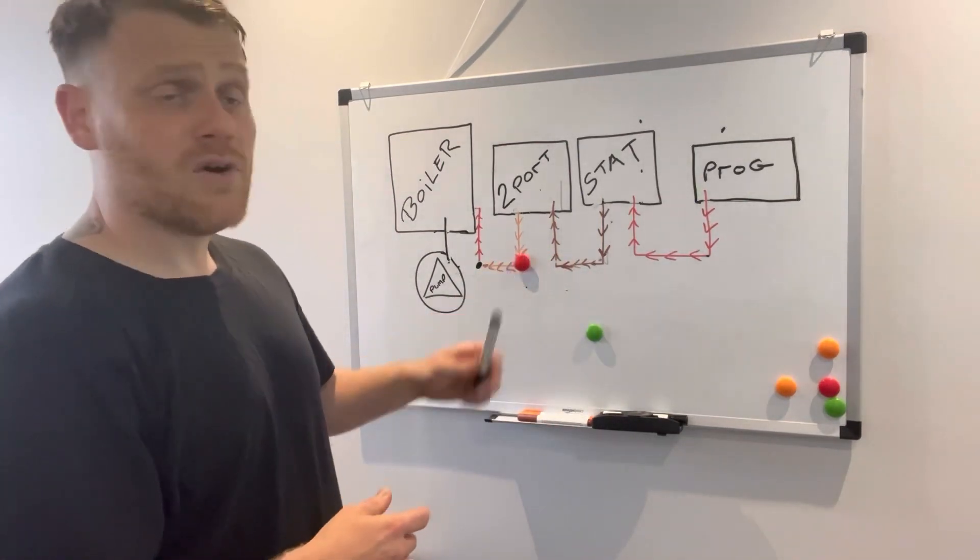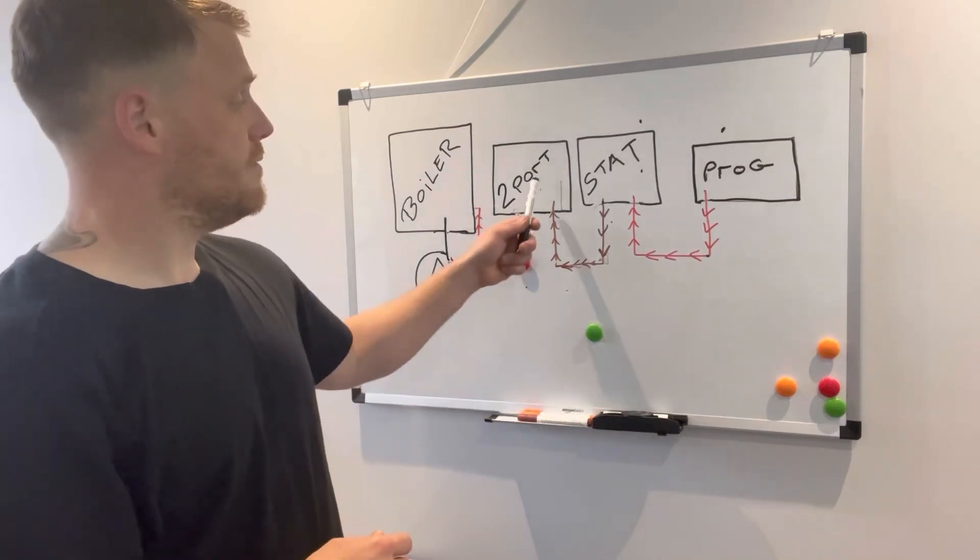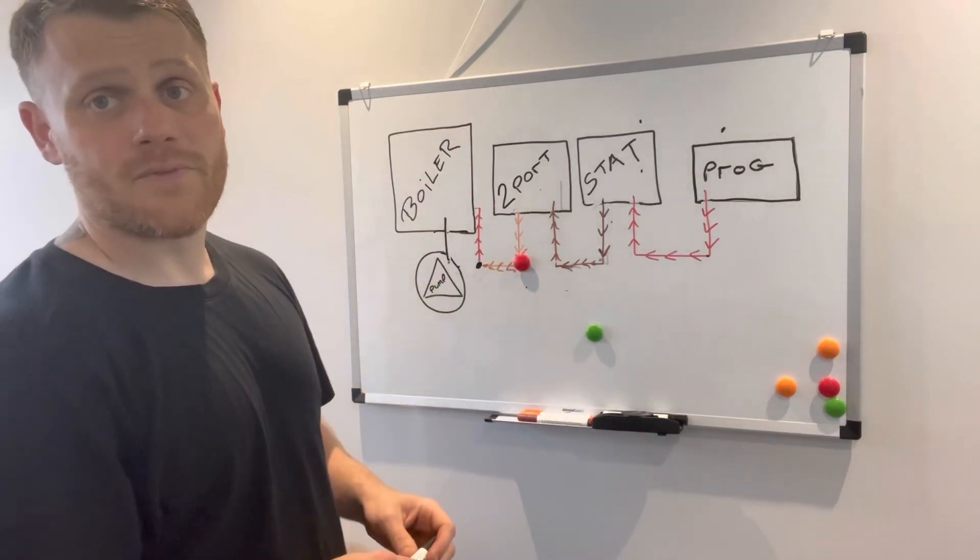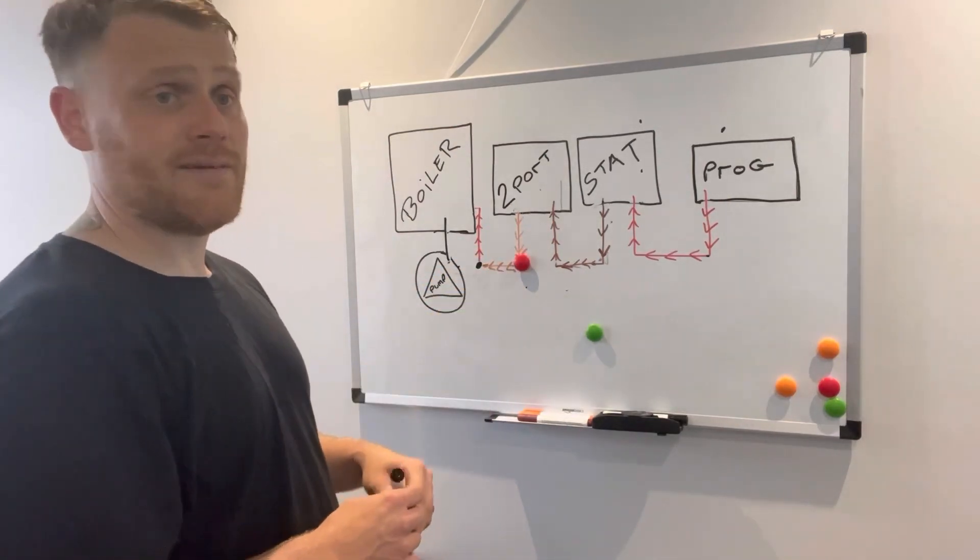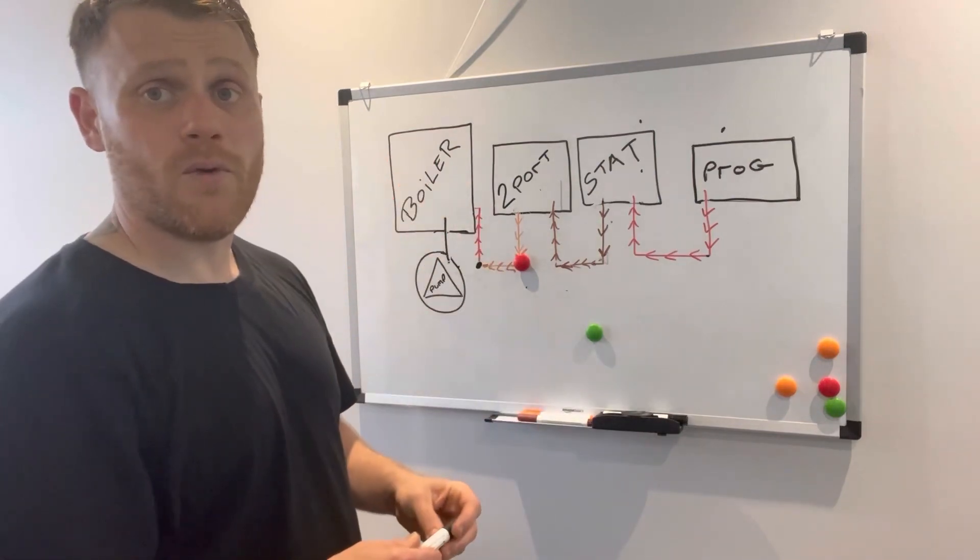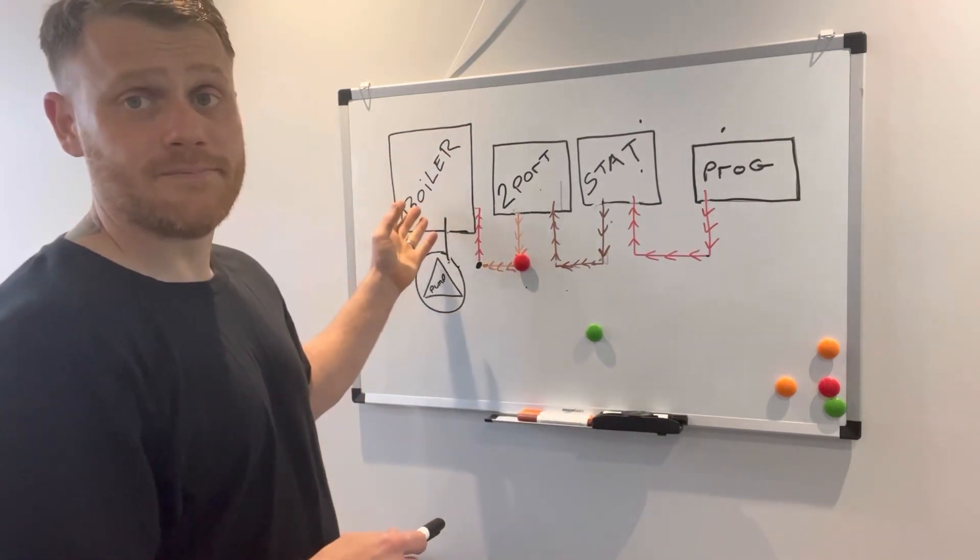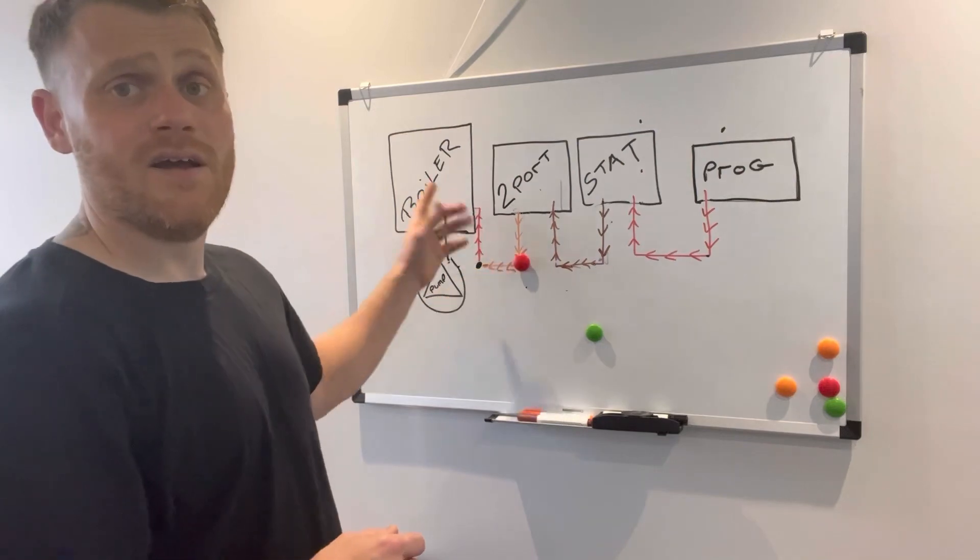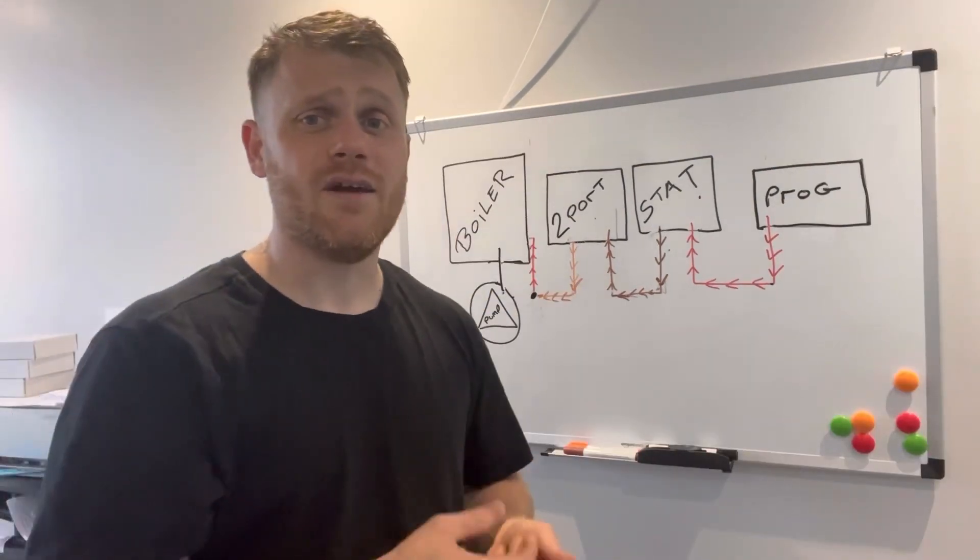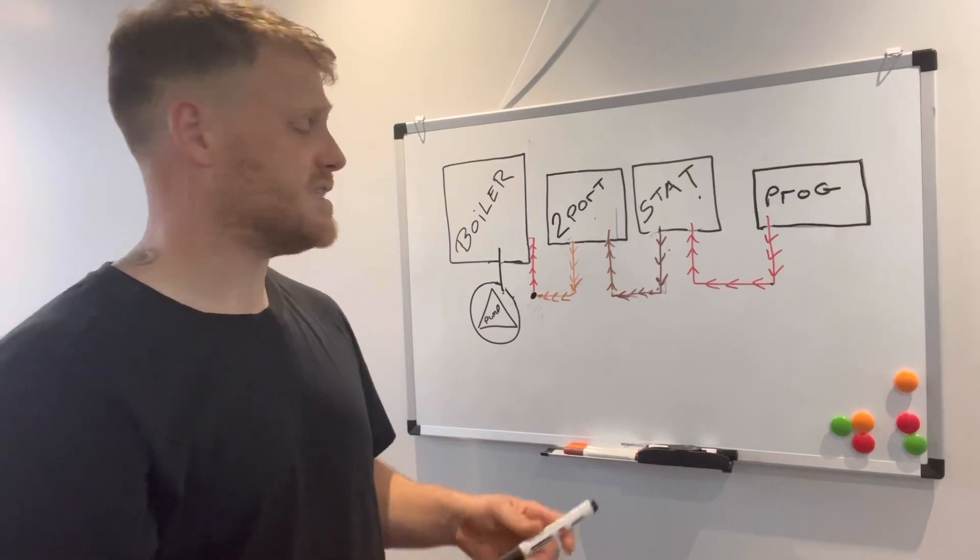Once I know I've got 240 on my brown, have I got 240 on my orange? If I haven't got 240 on my orange, I know then it's probably the two-port. If I have got 240 on my orange, then I know that there's something wrong with the boiler.